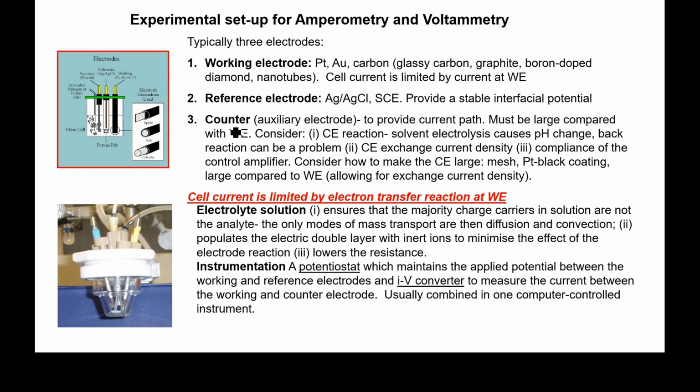That may not matter, but you definitely need to know this. Conversely, if you're doing an oxidation reaction at your working electrode, your counter electrode reaction pH will be going up. And if you're trying to do long-term measurements over days in an implanted device, you definitely need to think about this, because you're going to be getting high pH regions that are going to hydrolyze the tissue around the counter electrode and possibly cause extensive damage.